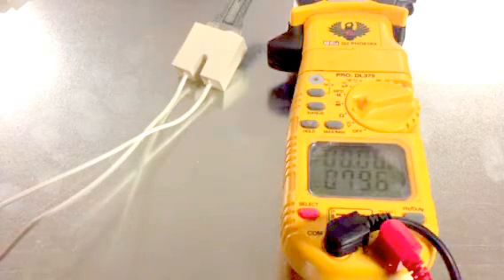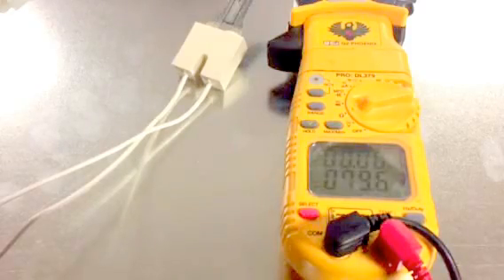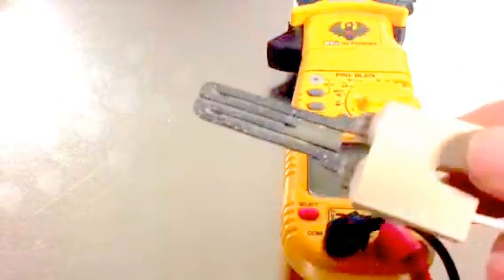The main thing is anything over a hundred, you want to recommend replacement because something's probably going wrong. There's more resistance than there should be and it's probably going to burn out and crack. Normally these will get a little hairline fracture in them, sometimes they'll break completely apart when they short out.